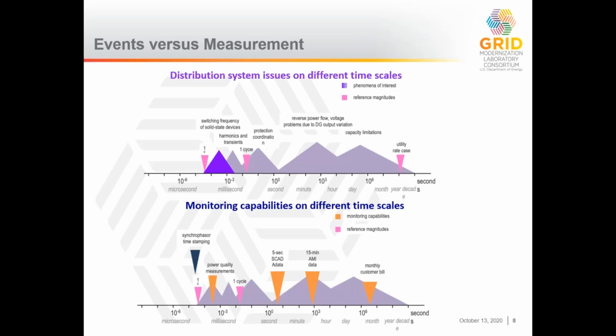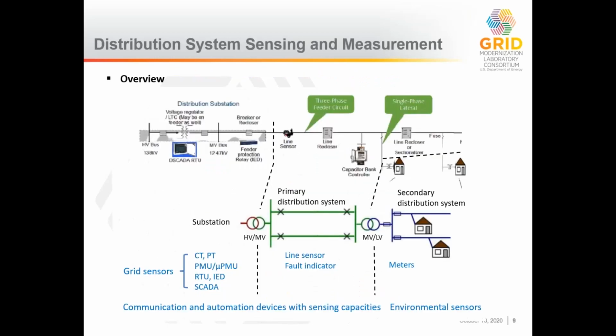Next slide. I'm summarizing here just the types of sensors you see at different levels. Grid sensors include things like current transformers and potential transformers at the basic level, phasor measurement units and micro phasor measurement units, which measure voltage and current, magnitude and phase angle, giving you directional type flow information to work out deviations and things like power flow from the phase angle data.